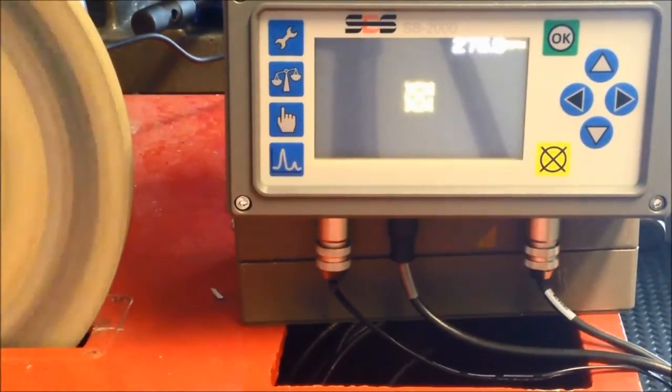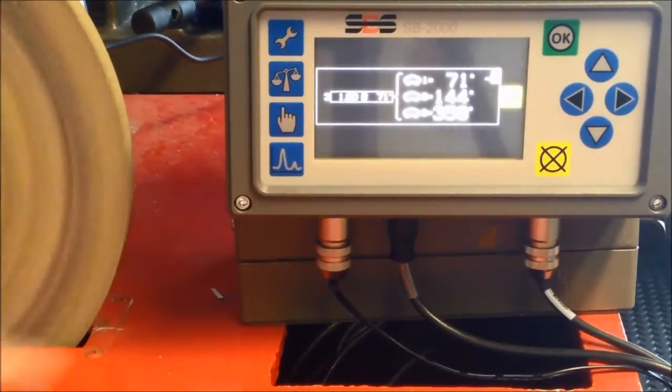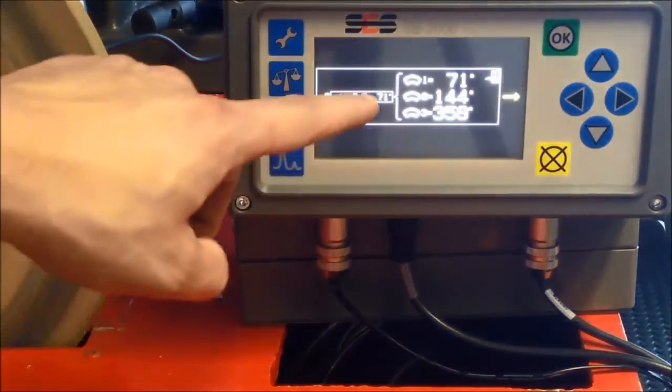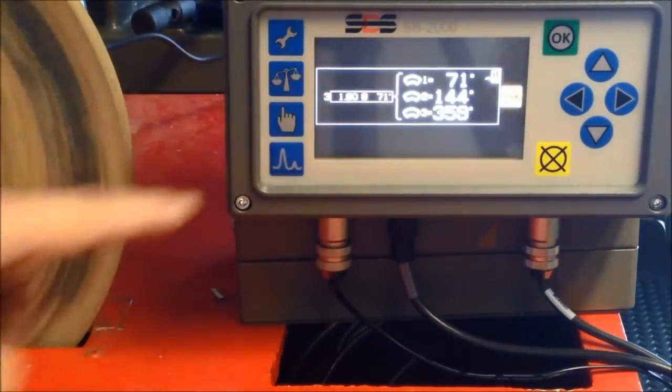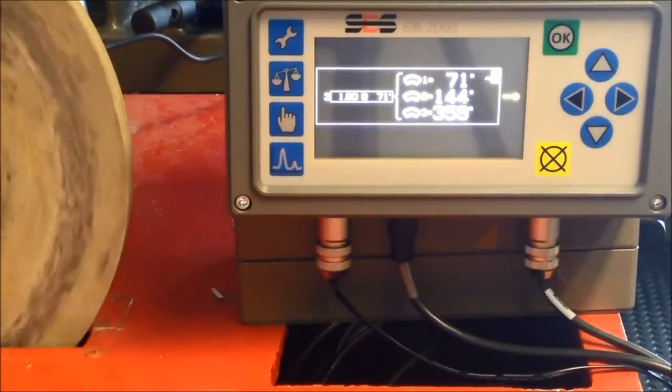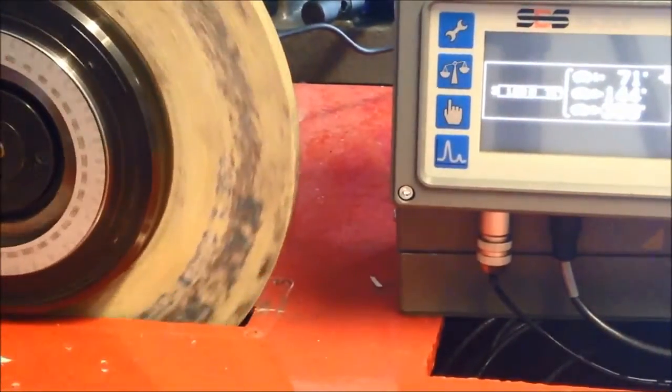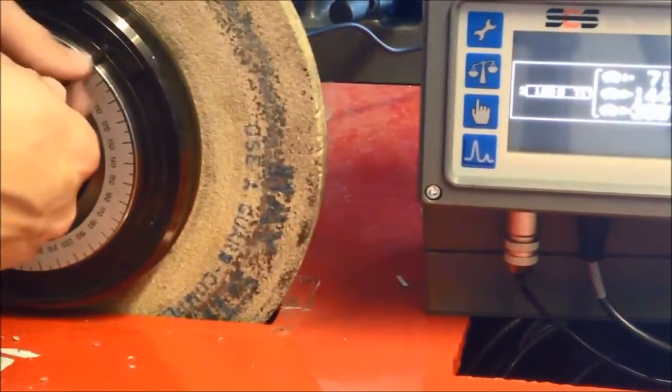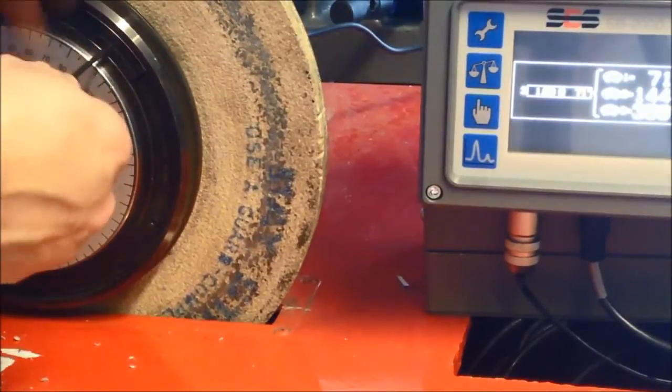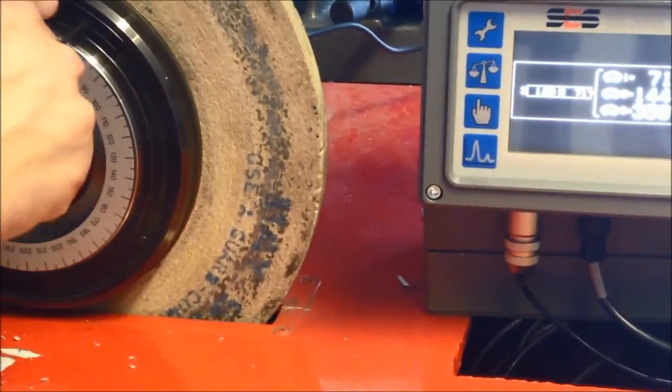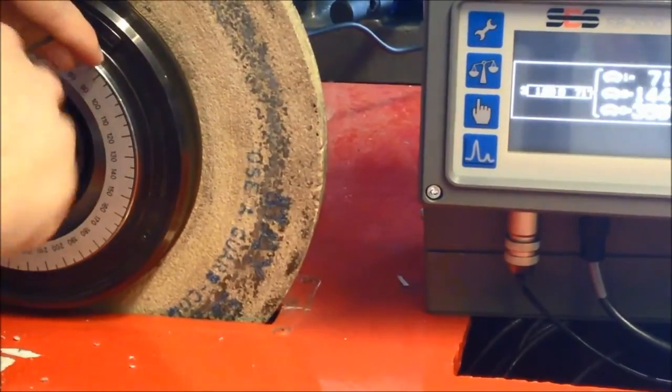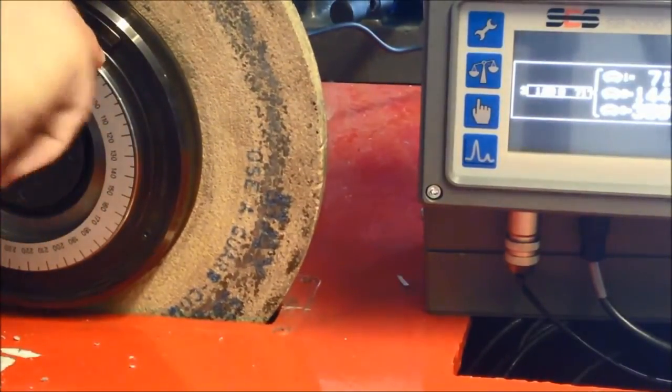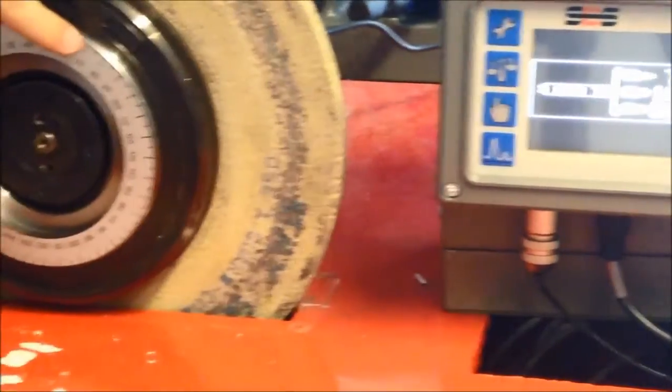Here we have the solution phase. Having carried out a zero run and a test run, the SP2000P will tell us at what angle to place the weights in order to achieve a final balancing solution. In this case 71, 144, and 359 degrees.